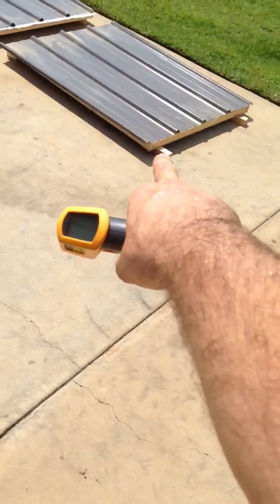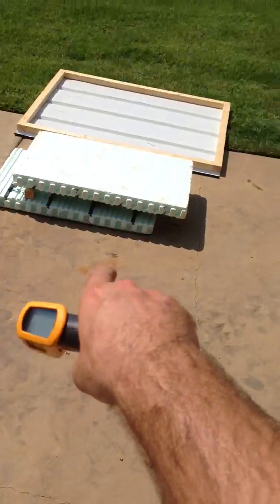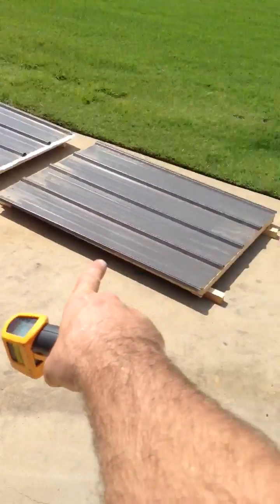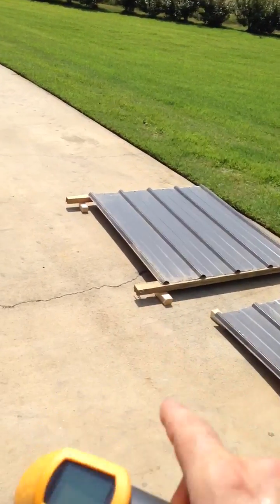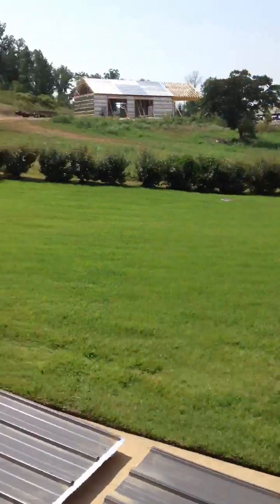So what's the point? Very few people are going to put three-and-a-half-inch thick insulation in these buildings when you can get bubble wrap for pretty cheap. The bubble wrap, if it's installed correctly, almost does as good a job as the thick panel. Putting it underneath the steel does work, but it does not work as well as putting an air gap. And a pole barn with no insulation doesn't hardly do anything.